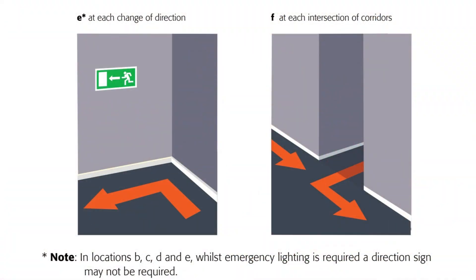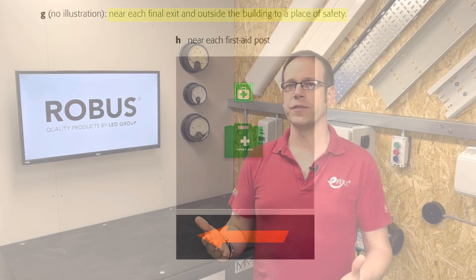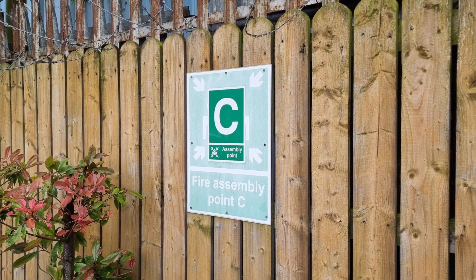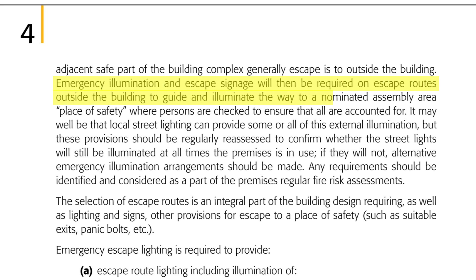Over the page we find more examples of where escape lighting luminaires are needed, including at each change of direction and intersection of corridors to stop people running into walls and other people. A critical and sometimes overlooked point: near each final exit and outside the building to a place of safety. It's not enough just to get people to the great outdoors — we need to get them to the assembly point. Emergency illumination and escape signage will be required on escape routes outside the building to guide people to a nominated assembly area where all persons are checked to be accounted for.